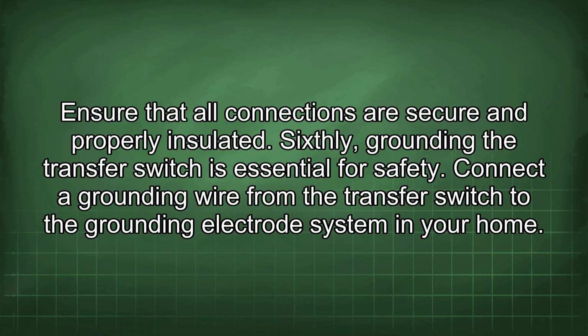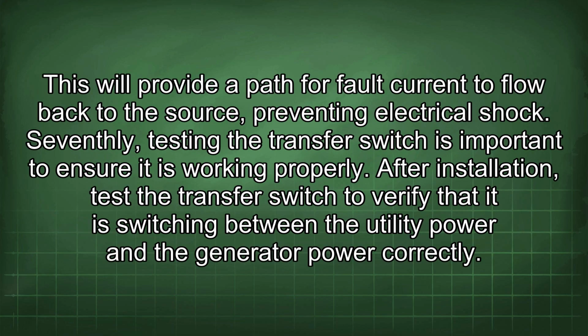Sixthly, grounding the transfer switch is essential for safety. Connect a grounding wire from the transfer switch to the grounding electrode system in your home. This will provide a path for fault current to flow back to the source, preventing electrical shock. Seventhly, testing the transfer switch is important to ensure it is working properly.